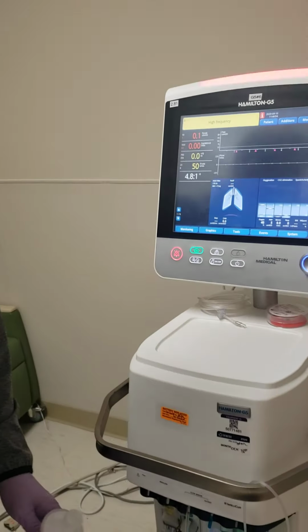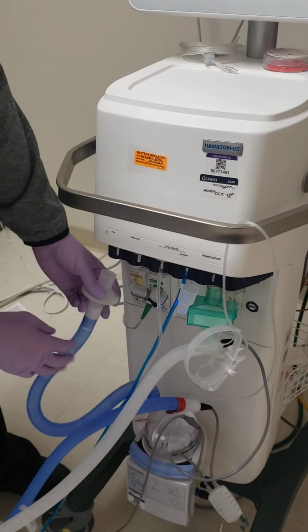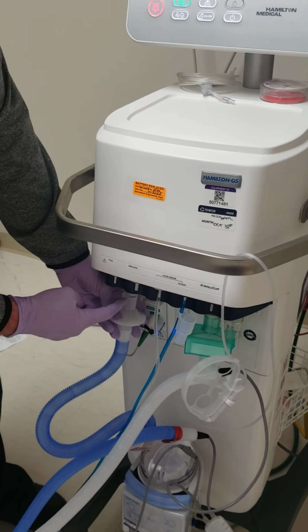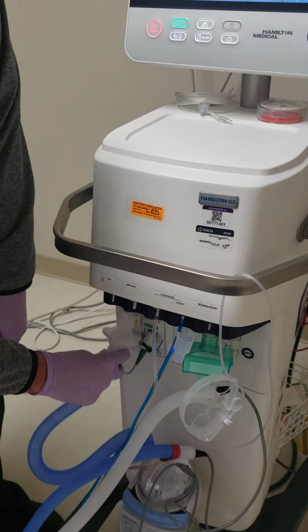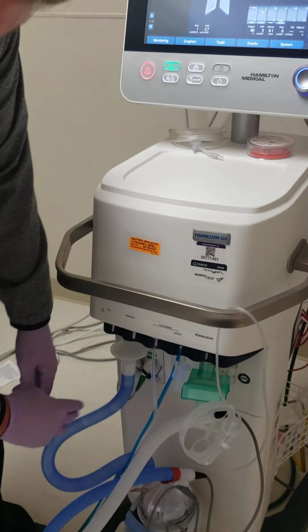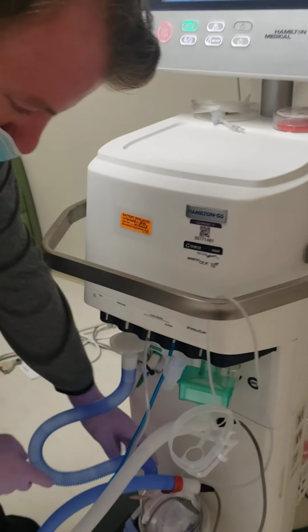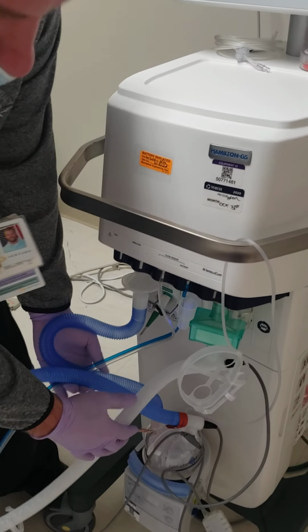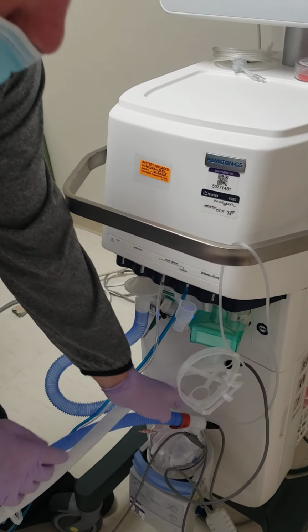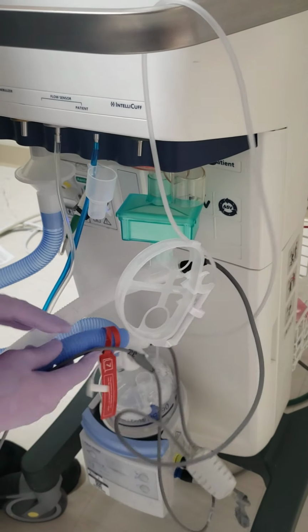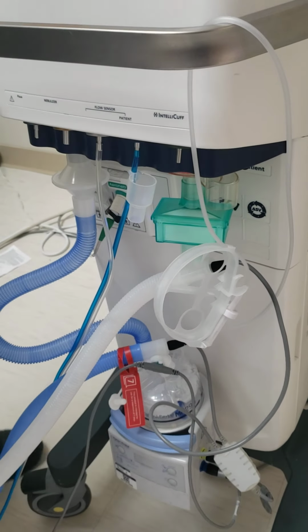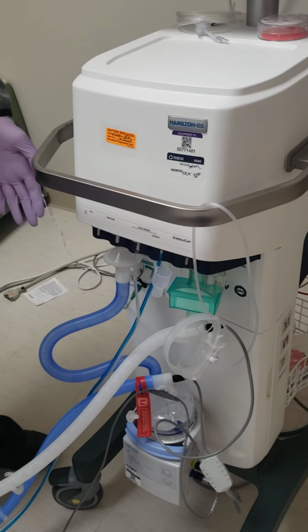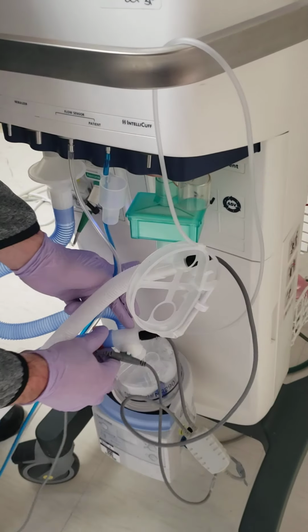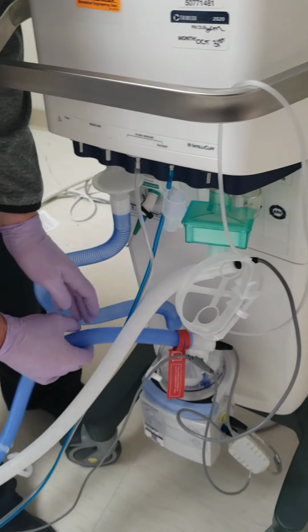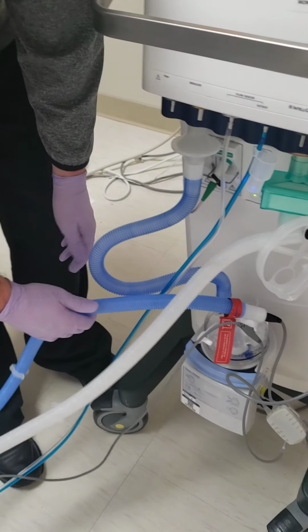That means you probably have a disconnect on your ventilator. The best thing to do, start from left to right. Start at your circuit. If this is the problem, just put it back on. If this is not disconnected, follow down. It could be disconnected on your heaters down here. One spot that's very tricky, sometimes this one becomes disconnected, but it'll sit right there and it looks from the top like it's connected. Reconnect. If it's not here, here, here, keep following your circuit.